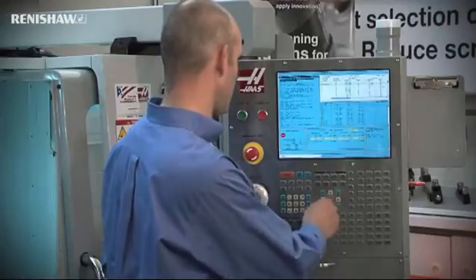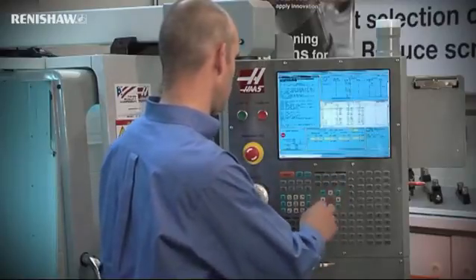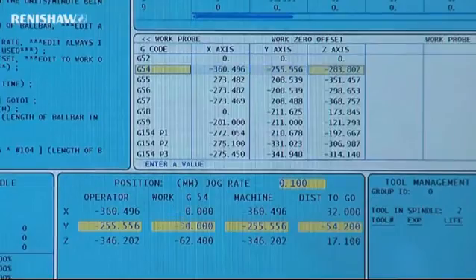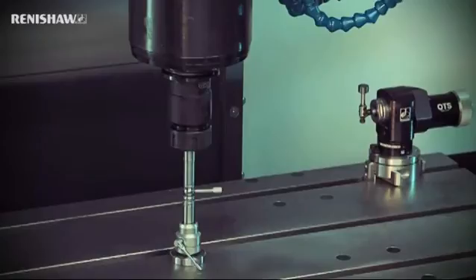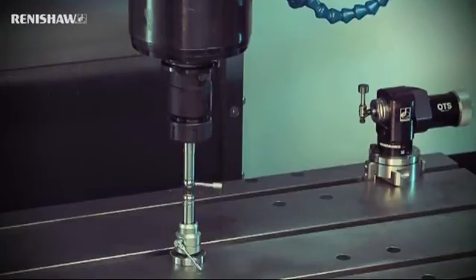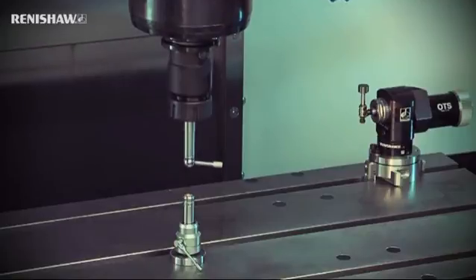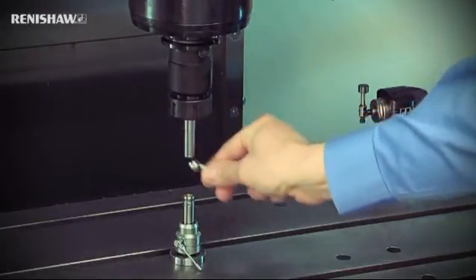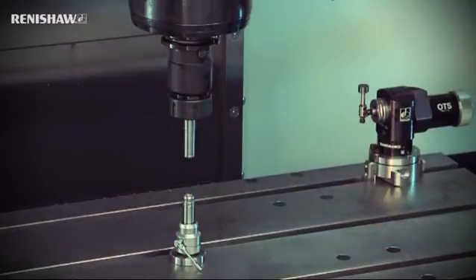Establish the G54 offset so that the current position is X0, Y0, Z0. Jog the Z axis up so that you can remove the setting ball. Take care to ensure that only the Z axis moves and that it is in the positive direction. Remove the setting ball and put it back in the storage case for safekeeping.